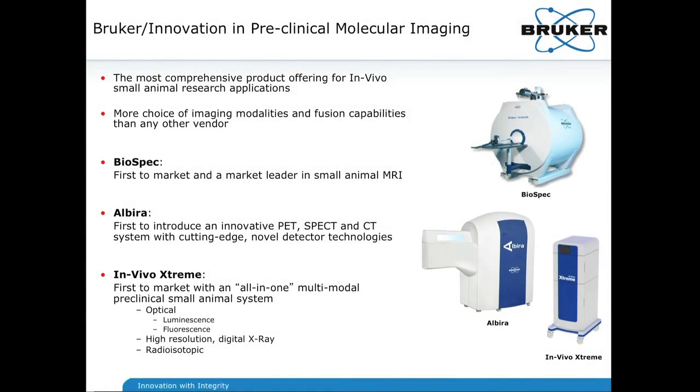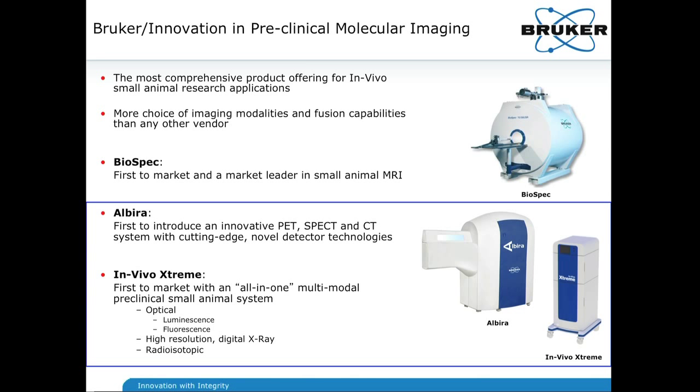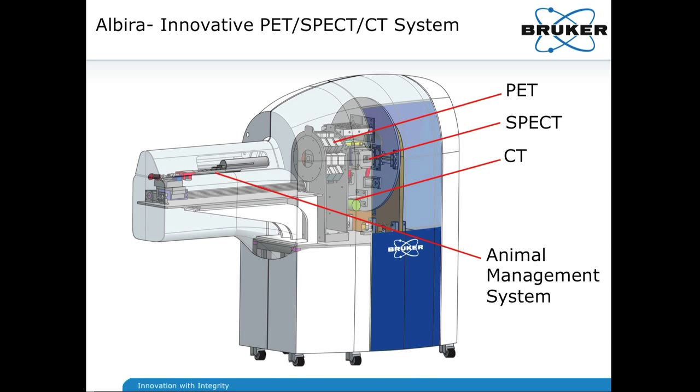The focus will be on the Albira and the In Vivo Extreme. Here's a quick peek inside the Albira. It basically consists of a lead-shielded, tri-modal, modular construct with a ten-and-a-half centimeter gantry for the animal management system. It can handle one or four mice — the four-mouse handler is a holder in progress — or alternatively one rat. This is a heated, anesthetized chamber with video cam access for animal management purposes, finely controlled for progression through the PET, SPECT, and CT modal sub-compartments of the Albira.